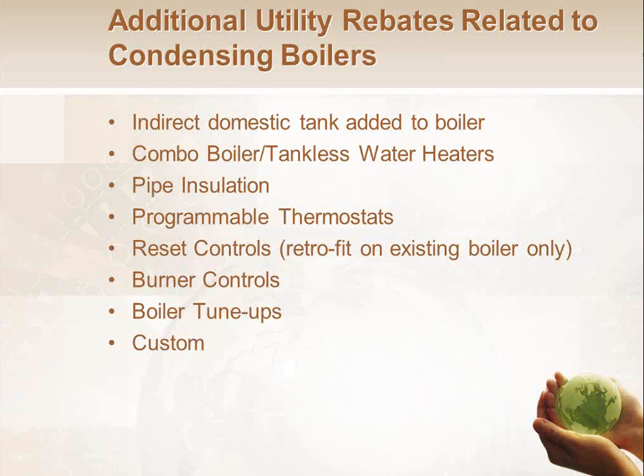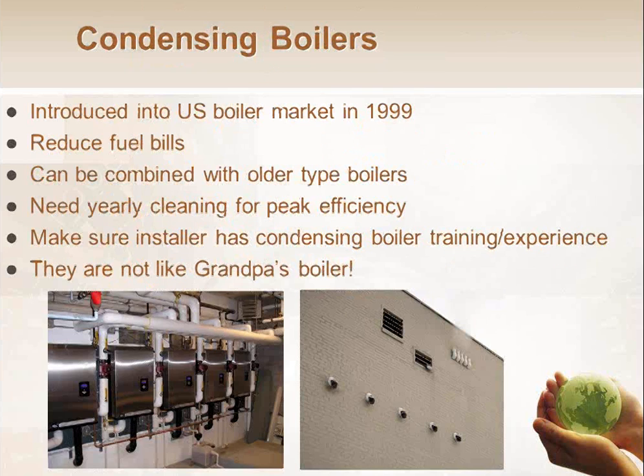But if you add outside air reset controls to an existing boiler, that's typically rebatable. And some of the utilities have rebates now for various burner control options, linkageless controls, high turn down burners, stuff like that. And pretty much everybody's got rebates for tune-ups commercially, and a few are even doing it residentially as well. If you need more information on the rebates, we have a whole 1-hour recorded webinar on that on our website if you want to learn about all the specifics for the various rebate programs.